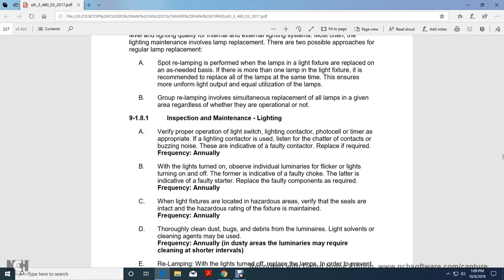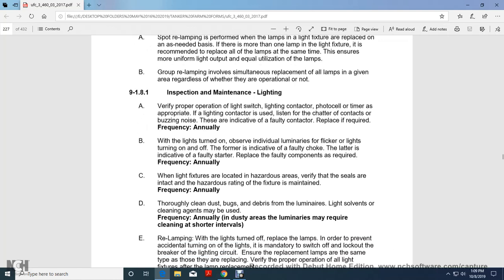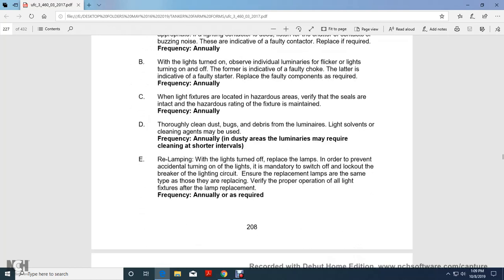Inspection and maintenance of lighting. Verify operation of the light switch, lighting contactor, photocell, and timer, as appropriate to the lighting contactor used. Listen to the chattering contactor's buzzing noise, which indicates the contactor needs replacement, annually. With the lights turned on, observe the individual luminaires for flickering when the lights turn on and off. Flickering is indicative of a faulty choke, later indicating a faulty starter. Replace faulty components as required annually. When light fixtures are located in a hazardous area, verify the seals are intact. The hazard rating of the fixture is maintained annually.